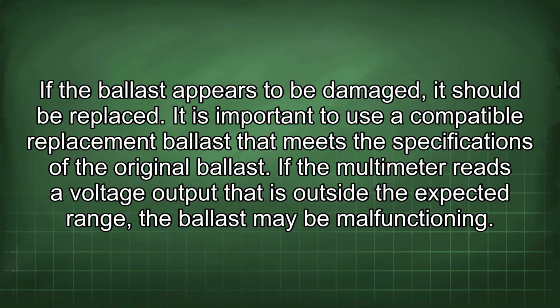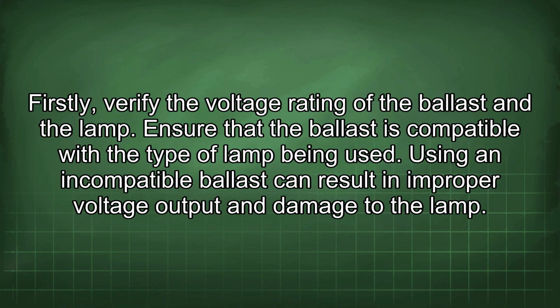If the multimeter reads a voltage output that is outside the expected range, the ballast may be malfunctioning. Firstly, verify the voltage rating of the ballast and the lamp. Ensure that the ballast is compatible with the type of lamp being used. Using an incompatible ballast can result in improper voltage output and damage to the lamp.